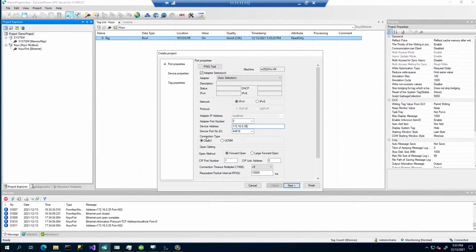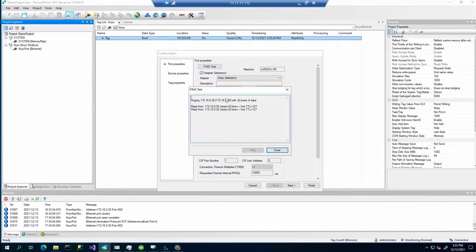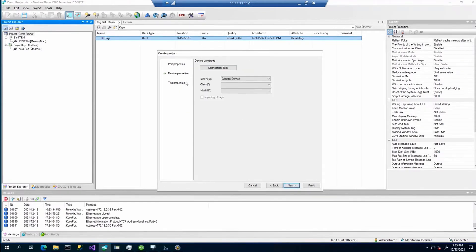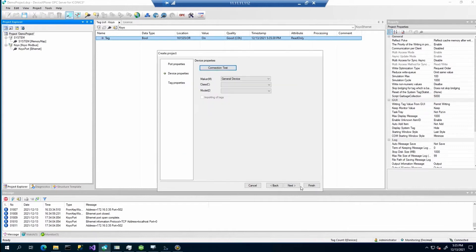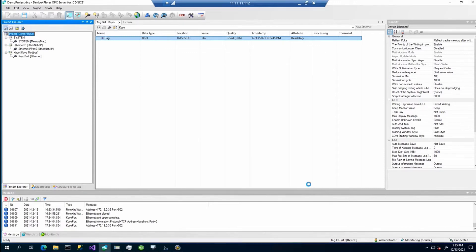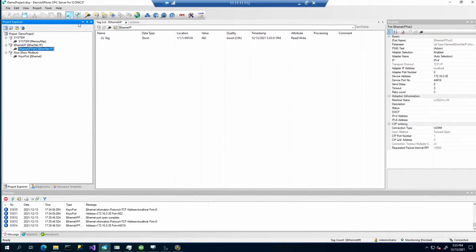Unfortunately, it supports only this connection type. The class 3 is not supported. And again, we can check the ping. It's OK. Hit next to the device properties. Here we don't need to change anything. And the connection is again OK. So we can specify some tag. And there is already one tag with this configuration. So we just click finish. And here we can see that the Ethernet IP project was created with this tag.